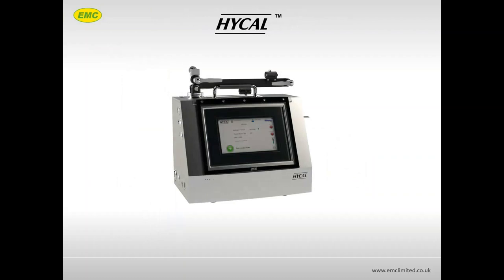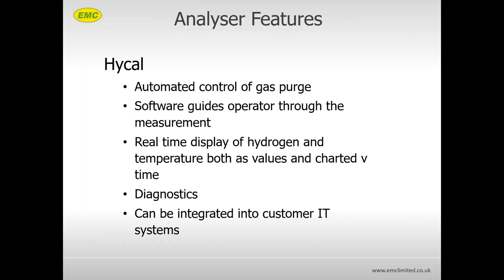Firstly, Hycal itself, which is becoming well established in the wrought aluminium industry. It's a fully automated unit, very easy to use. The control of the gas purge is automated. There is software which guides the operator through the measurement step by step. It will display in real time hydrogen concentration and temperature, both as values and charted versus time. There's onboard diagnostics which constantly monitor the condition of the probe and will alert the operator to any potential problems and give some advice on how to resolve those problems. And it can be easily integrated into customer IT systems, so it can be linked directly into quality control systems.